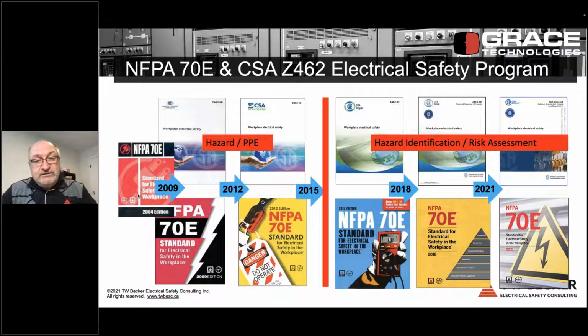The other big change is that in the 2015 editions, both standards became 100% risk assessment based. This is a game changer and the right decision, aligning with occupational health and safety management systems. But I find a lot of arc flash and shock training doesn't discuss the risk assessment procedure itself, focusing only on the two unique risk assessments in 70E and Z462: the shock risk assessment and the arc flash risk assessment.